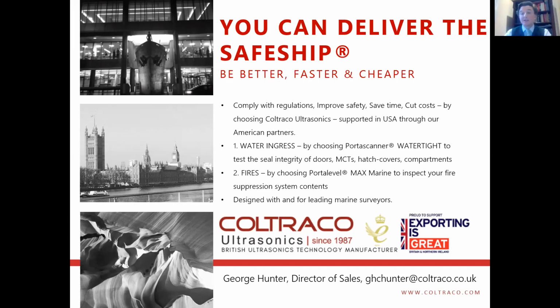Yes. All of our equipment really is classified under international standards as safety equipment. Now, all safety equipment is required to be calibrated annually, and so as such, we comply with those standards, and we always recommend it is annually calibrated. Of course, it is completely at your discretion, and as I mentioned, we do have service stations in the US as well. But every unit we provide comes with what we call a function test in the instructions, and as long as that function test continues to pass, the unit is fit for purpose and can be used knowing it is working well. But again, under the letter of the law on the certification side, we must recommend annual calibration. You provide the certification for that, because you're always asked that.